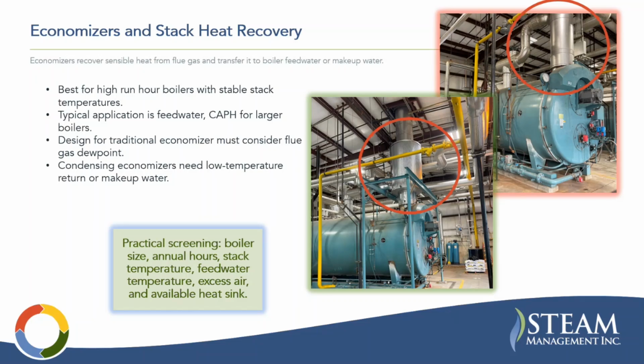Combustion air preheaters are common for larger boilers. The design for a traditional economizer must consider the flue gas dew point, so you don't want to unintentionally turn your boiler into a condensing boiler. And then condensing economizers typically need another low temperature process, or possibly preheating makeup water into the system if there's a significant makeup water stream.